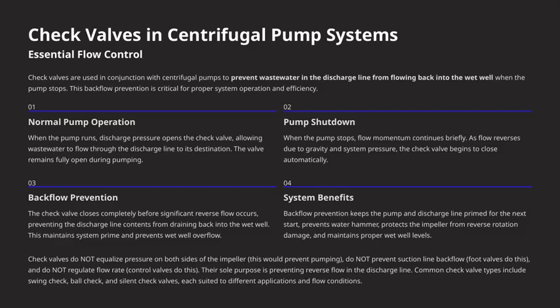Once the pump shuts down, the flow momentum doesn't stop instantly. Instead, it continues briefly due to inertia. As the flow begins to reverse, driven by gravity and system pressure, the check valve automatically starts to close. The key point here is that the check valve closes completely before any significant reverse flow can occur. This prevents the contents of the discharge line from draining back into the wet well. By doing so, it helps maintain the system prime and prevents overflow in the wet well.